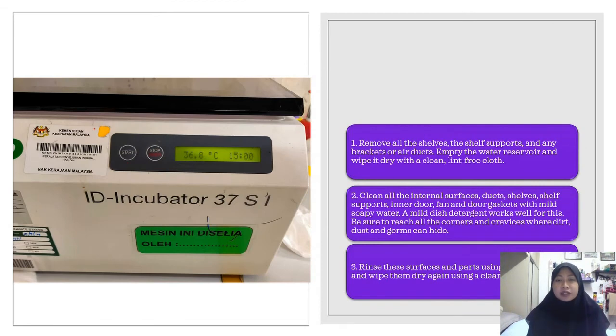Next, this is the step about how to clean the incubator. I'm showing you the incubator that is used in my laboratory. First of all, you need to remove all the shelf supports and any brackets or air ducts, and empty the water reservoir and wipe it dry with a clean lint-free cloth.